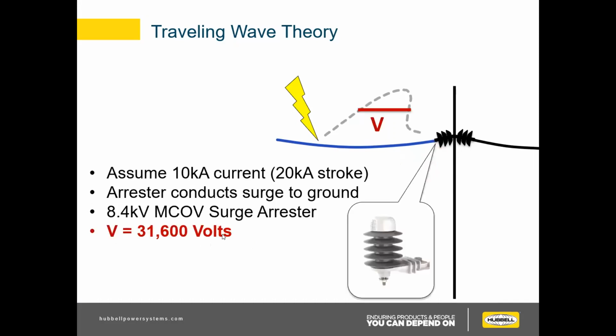So when we have a surge arrestor in place, that outcome is going to be much different. So let's say that same 10 kA stroke travels down the line, and the arrestor has a given discharge voltage for a 10 kA stroke. So in this case, for an 8.4 kV MCOV surge arrestor, the arrestor will discharge 31.6 kV. So as long as this insulator or transformer has a BIL of over 31.6 kV, you're never going to know anything happened. It's going to be fine. The transformer is going to be protected, and you're never going to know any lightning stroke, any hit anywhere. So that's the importance of a surge arrestor.